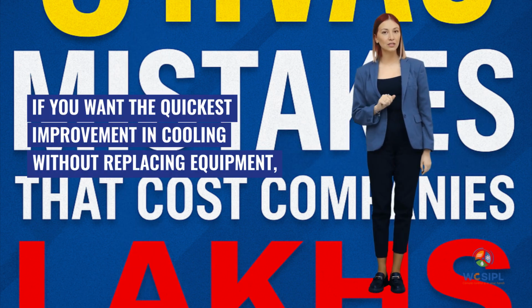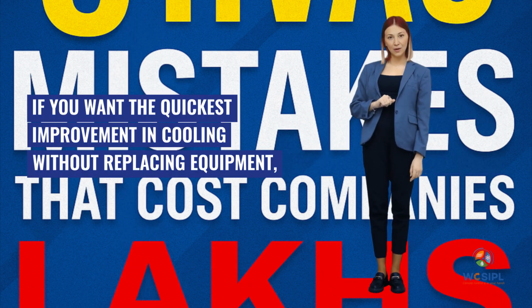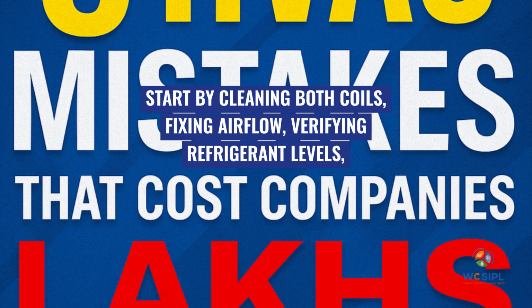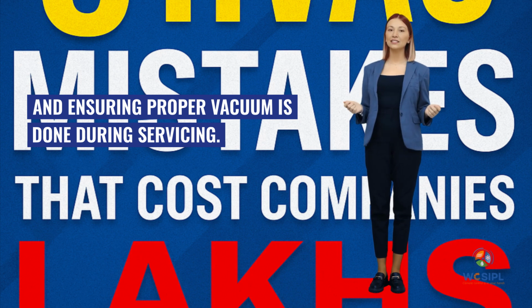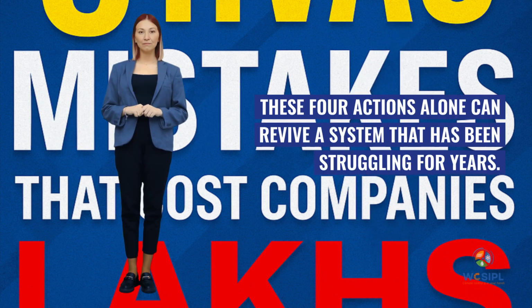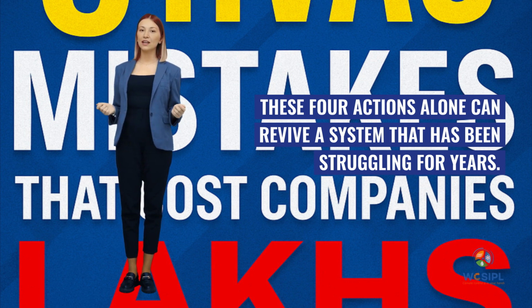If you want the quickest improvement in cooling without replacing equipment, start by cleaning both coils, fixing airflow, verifying refrigerant levels, and ensuring proper vacuum is done during servicing. These 4 actions alone can revive a system that has been struggling for years.